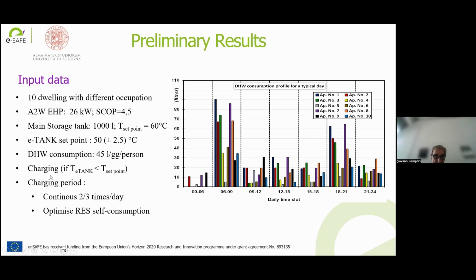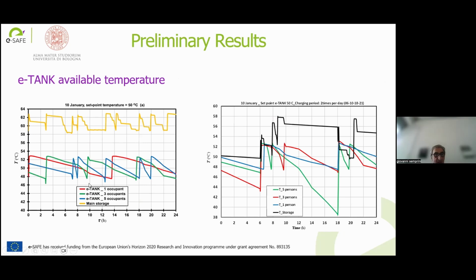In the preliminary simulation, we consider the charging of the tank when the temperature is lower than the set point temperature, and the charging period can be considered continuous or 3 times a day. Here are some results. First, when we decide to move from the traditional centralized system to the decentralized system, it is important to verify that the temperature is continuously available in each dwelling. Then we make a simulation, and you can see 3 different profiles of temperature of domestic hot water.